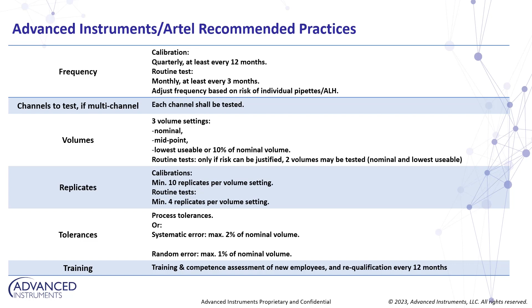Now, a robust calibration verification program often contains details about frequency, volumes, replicates, and tolerances. In summary, we recommend calibrating quarterly or at least every 12 months and performing routine tests every 3 months. Make sure that all multi-channel devices have each channel tested and that adjustable volume devices are tested at low, mid, and high volumes with 10 replicates per volume. Now, with regards to tolerances, they can take shape in many forms. Consider your process tolerances or establishing a systematic error of plus or minus 2% with a random error of less than or equal to 1%.